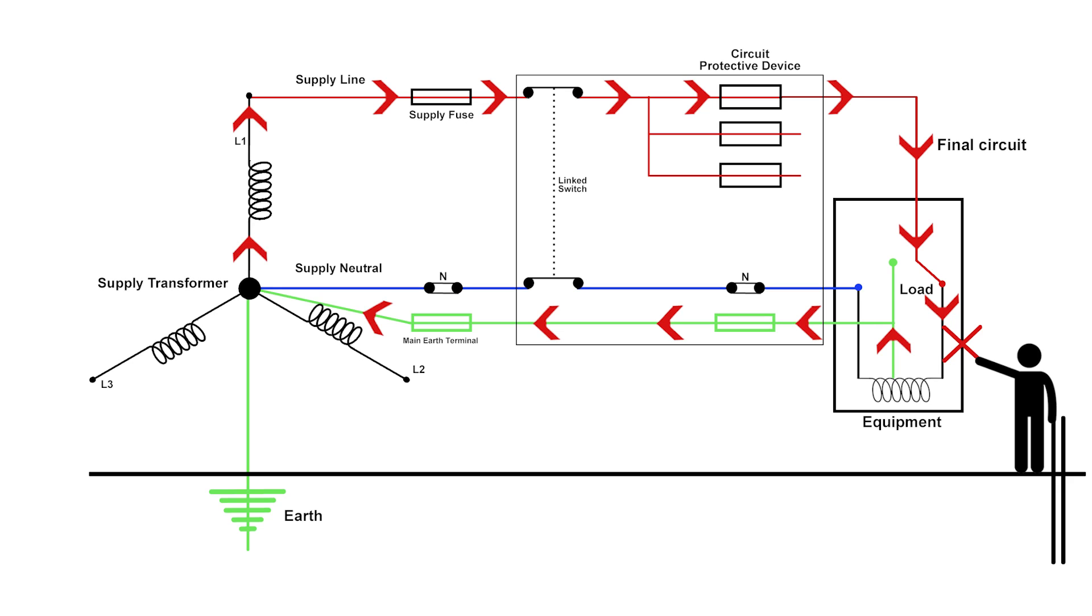Fairly obviously, for a hundred amps to flow, I need to have a reasonably low resistance. The easiest way to do the calculation, really, to find out what the maximum resistance would be, is to divide our voltage, which is 230, by 100, and we will end up with a resistance of 2.3. Now 2.3 would be the maximum resistance of this loop, and that would take into account any temperature rises and everything else, so that would be the maximum.